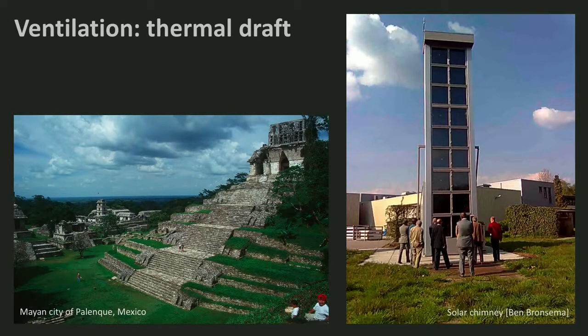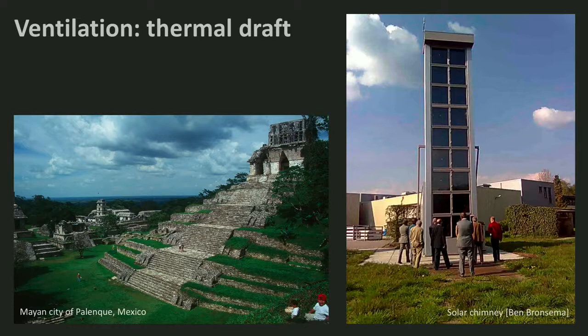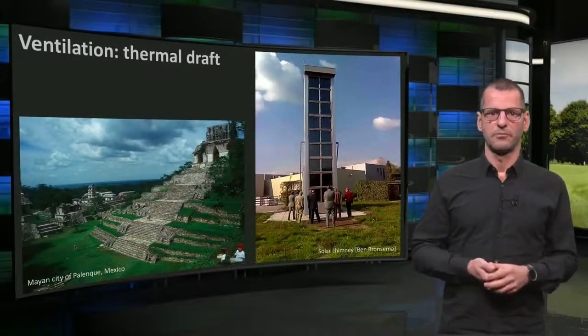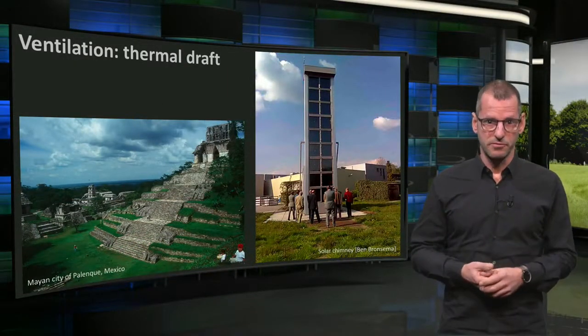Here you see a test model of one. A dark steel or stone slab behind a glass pane can induce a strong draft, creating under pressure below the chimney. Open a hatch or grill at the bottom and at the top, and a strong air flow will evolve. Although it will not always work — for instance when there is no sun — a solar chimney can help to ventilate the building without fans, hence save energy, and also to cool the building in a passive way.